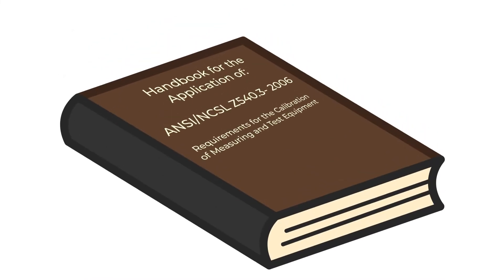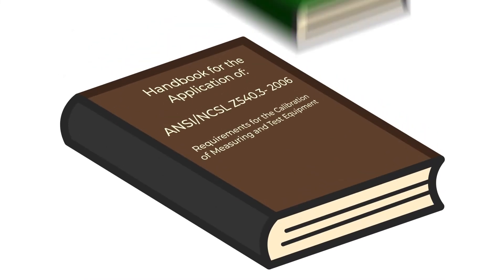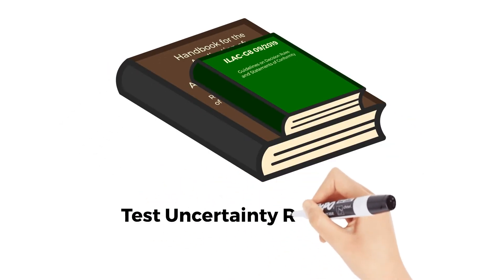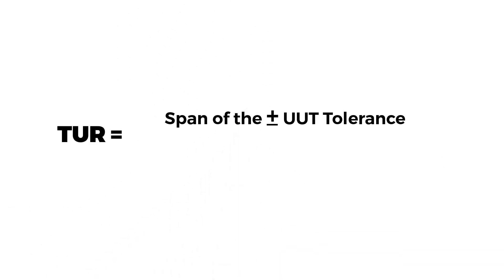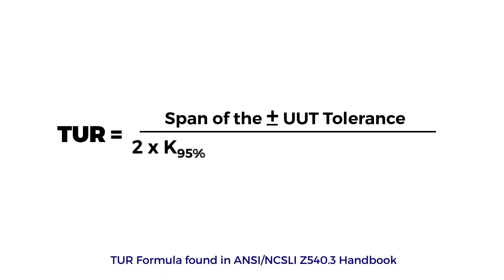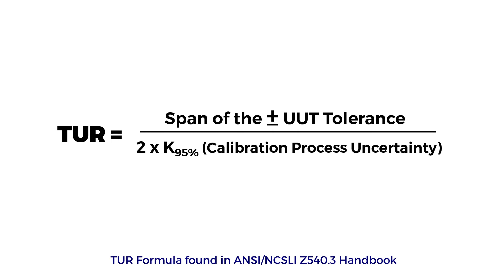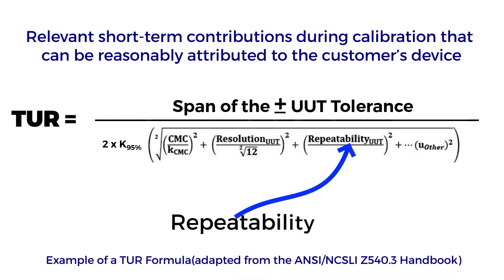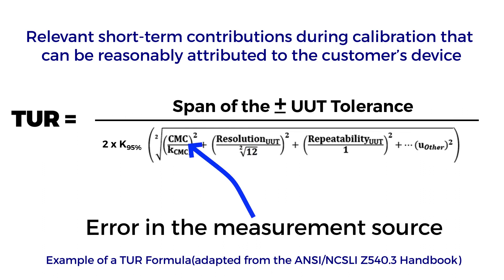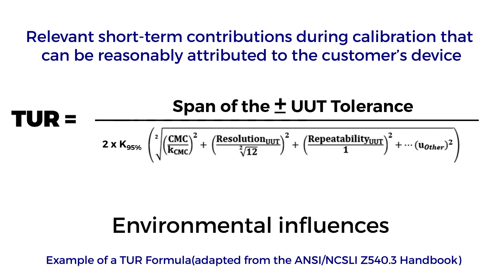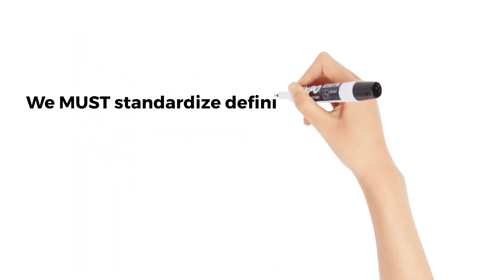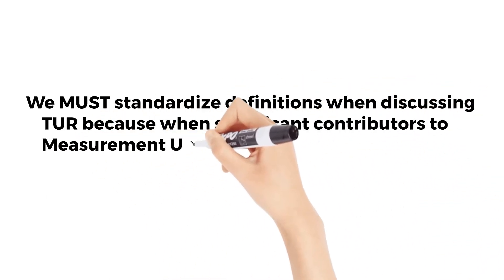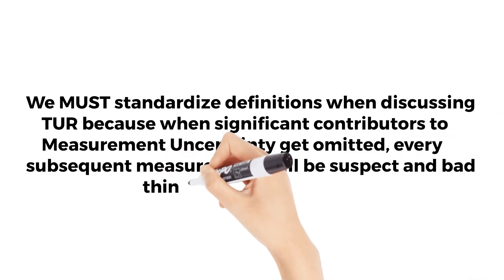Many of the decision rules found in documents such as the ANSI-Z540.3 Handbook and the ILAC-G8 use Test Uncertainty Ratio, or TUR, to help calculate their measurement risk. TUR is defined in the Handbook as the ratio of the span of the tolerance of a measurement quantity subject to calibration to twice the 95% expanded uncertainty of the measurement process used for calibration. The formula for TUR consists of the span of the tolerance in the numerator. The denominator includes short-term contributions incurred during the calibration, such as repeatability, resolution, error in the measurement source, operator error, error in correction factors, environmental influences, and others. We must standardize definitions when discussing TUR because when significant contributors to measurement uncertainty get omitted, every subsequent measurement will be suspect and bad things may happen.